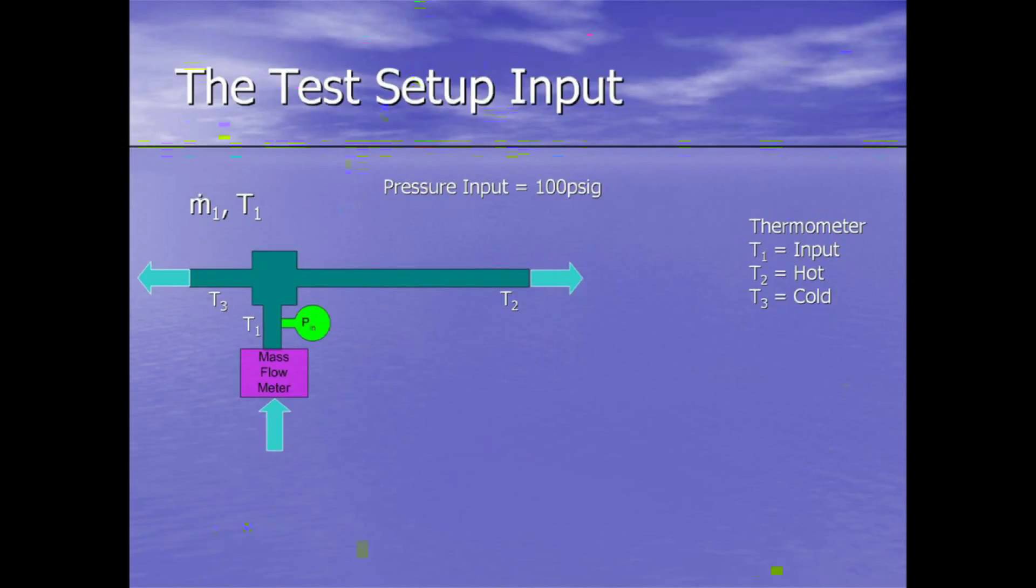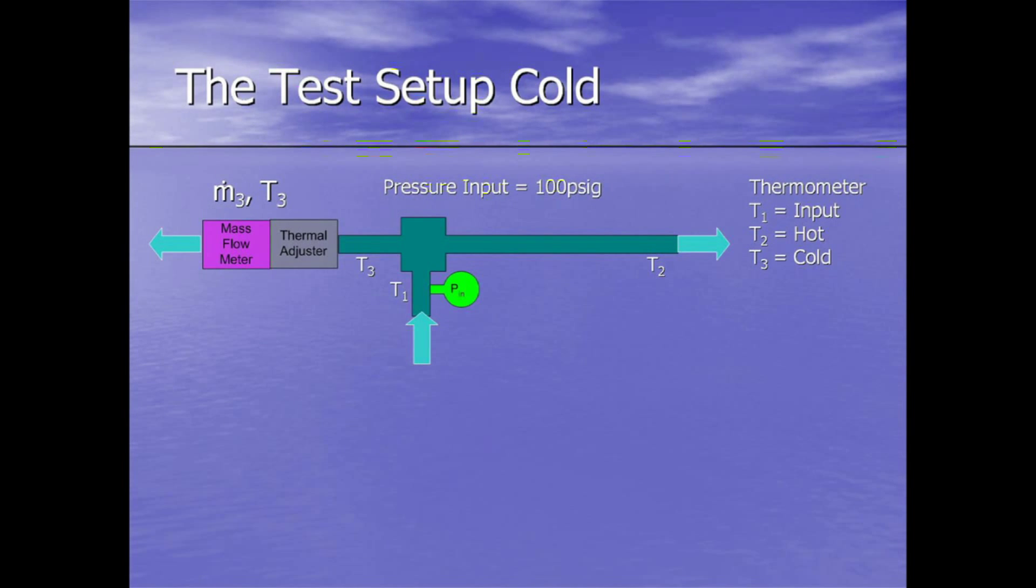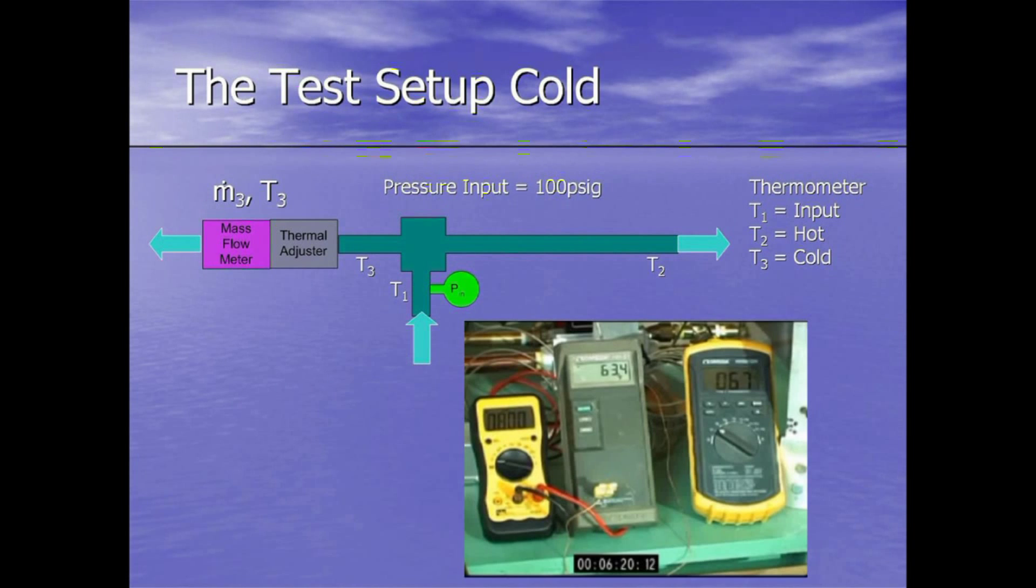The next three slides show the test setups for the input and the hot side and the cold side, and it shows that I've moved the mass flow meter around. The only critical input is the input pressure is 100 psi, and then the vortex allowed to reach stabilization wherever it decides to go. I had one limitation on my compressor. I had to bring it up to 120 psi, and we ran it until the compressor dropped to 105 psi. It couldn't quite keep up with the vortex tube.